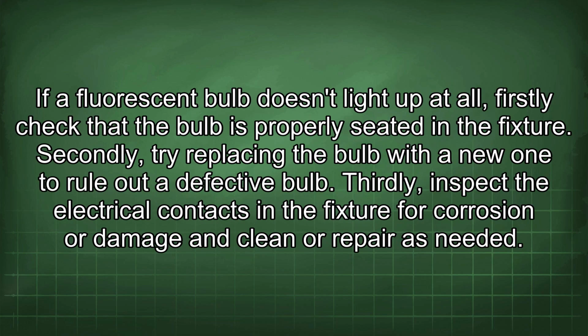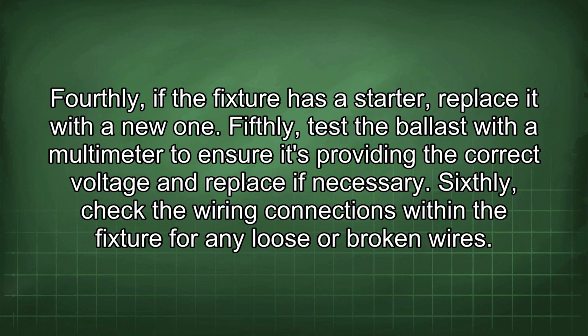If a fluorescent bulb doesn't light up at all, firstly check that the bulb is properly seated in the fixture. Secondly, try replacing the bulb with a new one to rule out a defective bulb. Thirdly, inspect the electrical contacts in the fixture for corrosion or damage and clean or repair as needed. Fourthly, if the fixture has a starter, replace it with a new one. Fifthly, test the ballast with a multimeter to ensure it's providing the correct voltage and replace if necessary. Sixthly, check the wiring connections within the fixture for any loose or broken wires.